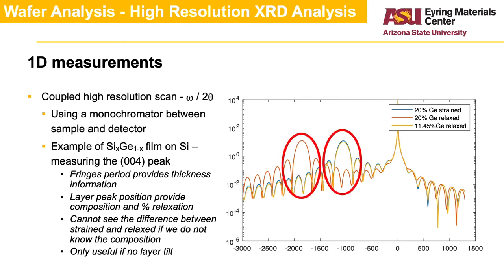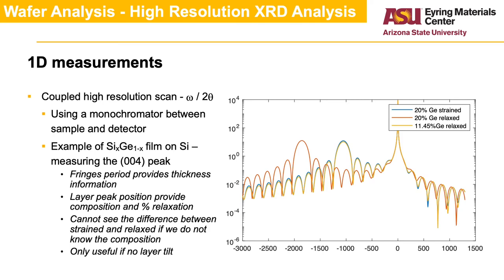The position of the layer peak is defined by the relaxation and the composition of the film. On this example, we can see that we can get a very similar plot for a strained film with 20% germanium and a fully relaxed film with 11.45% germanium. Therefore, a single omega-theta measurement may not be sufficient to provide the composition and relaxation without any other data. One should also point out that if the layer is tilted with respect to the substrate, the measurement becomes challenging and at times impossible using the triple-axis detector, which is the typical detector for such a measurement.